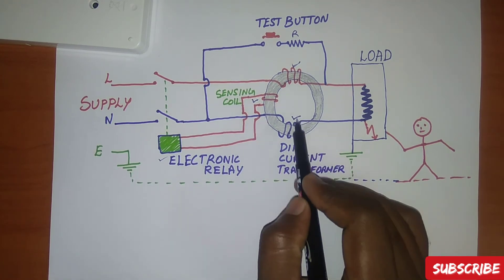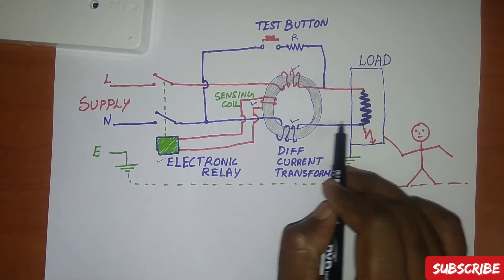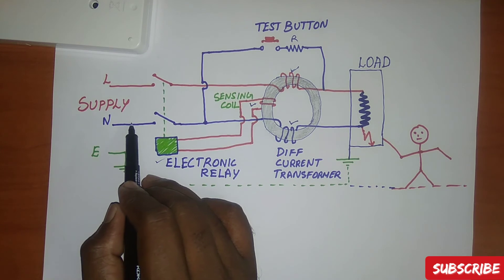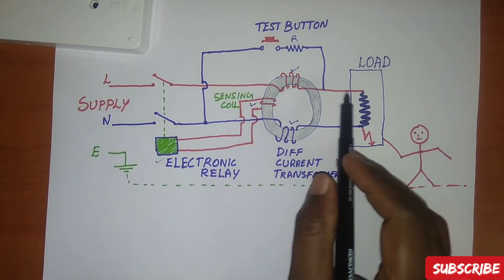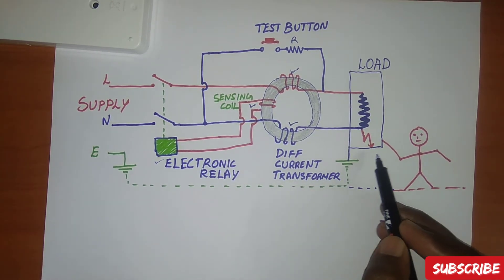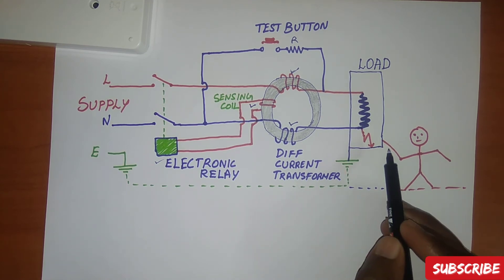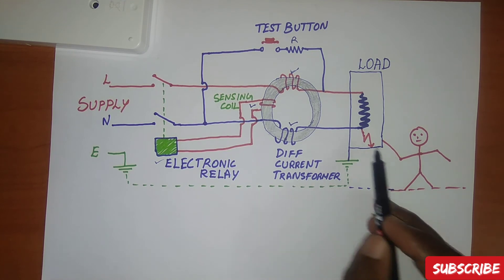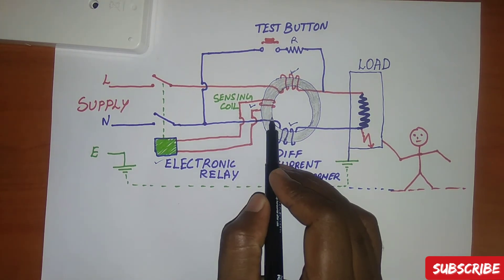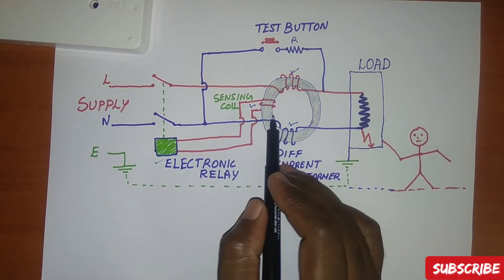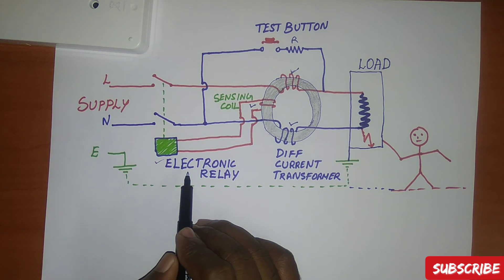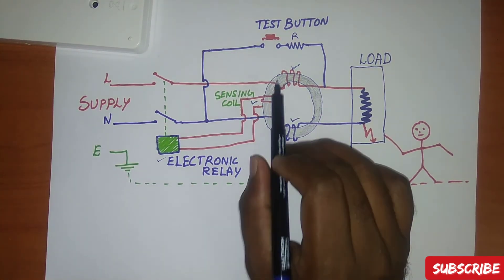The line and neutral cables are wound around the differential current transformer and directly connected to the load. In normal operation, all the current down the live conductor returns through the neutral conductor, so there is no difference detected in the current transformer. If any fault to earth occurs, or if a person touches a live component, some current takes a different path. This difference causes a current in the sense coil — the changing magnetic field induces current in it — which activates the electronic relay, disconnecting the circuit.